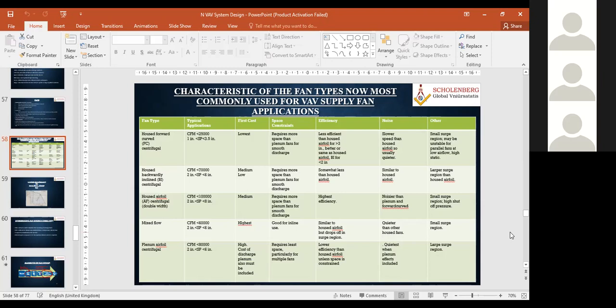Yes, and it is application to application. It is not necessary that we have to go for this one all the time; it all depends upon your design and selection. Though the standard suggests this, if you feel the plenum airfoil centrifugal has more advantage for the application, you can go for the plenum type too, especially if you want a higher capacity or bigger design. But in that case, you also have to compromise on noise level and acoustic treatment, depending on the industrial application.